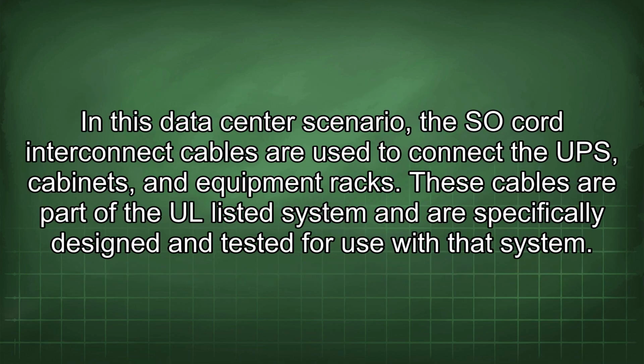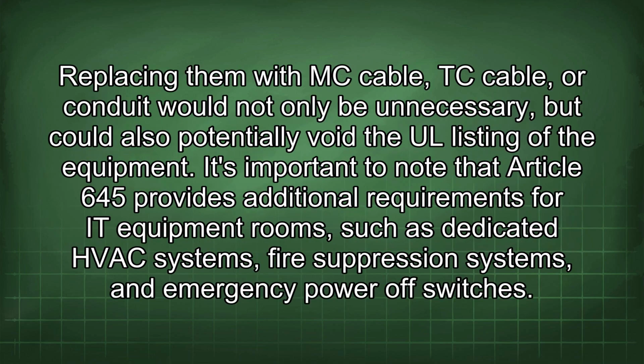In this data center scenario, the SO cord interconnect cables are used to connect the UPS, cabinets, and equipment racks. These cables are part of the UL listed system and are specifically designed and tested for use with this system. Replacing them with MC cable, TC cable, or conduit would not only be unnecessary, but could also potentially void the UL listing of the equipment.